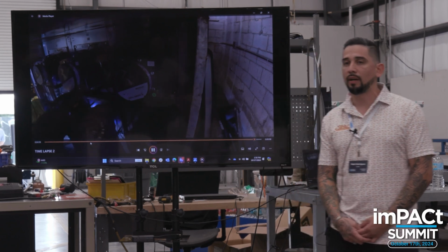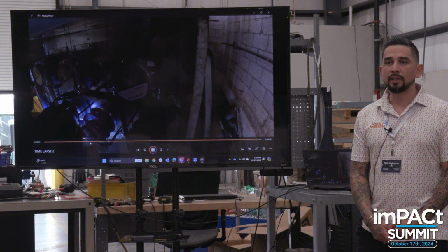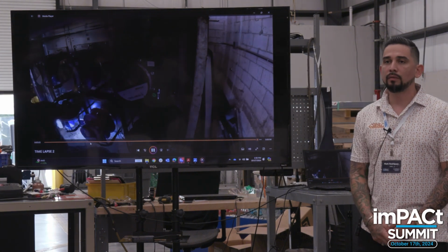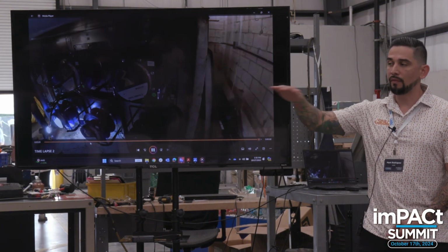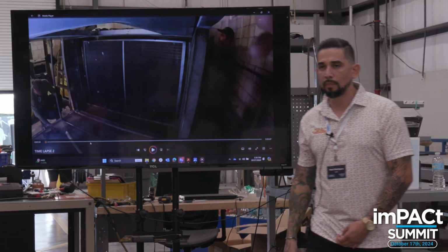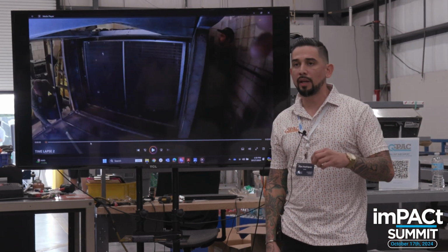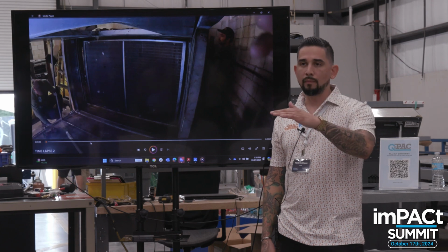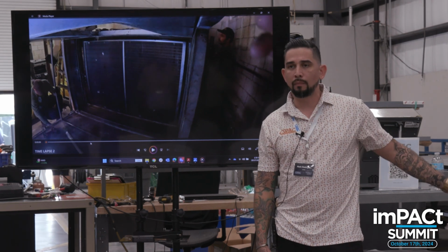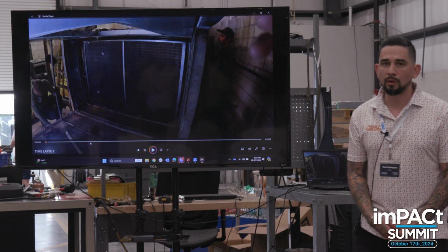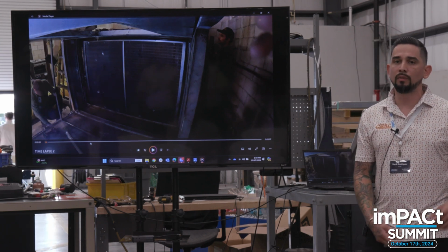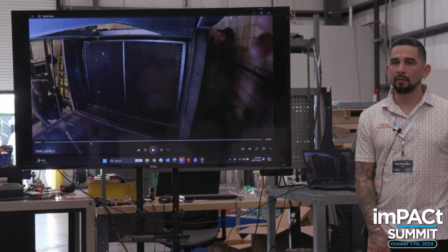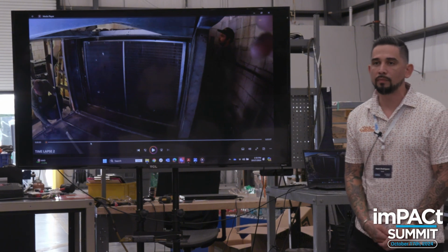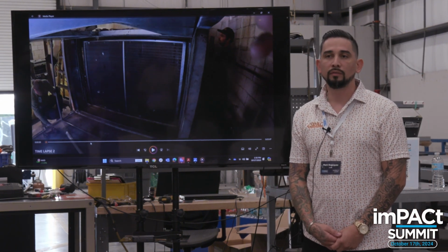Make sure you have all legs to ground before you engage that disconnect and feed it to the Q-PAC. As soon as you engage that Q-PAC, you want to make sure your safety circuit is made so it can engage the M1 contactor and get power to the motors. So you just want to make sure you've done your due diligence - conduit, bulkhead, screws - make sure everything is set in perfectly.